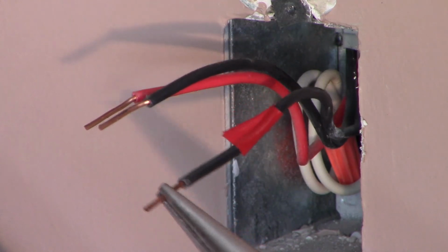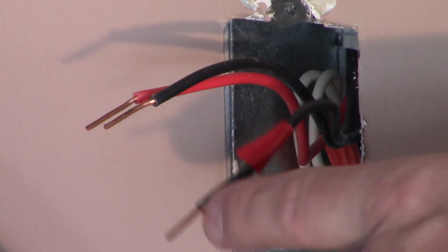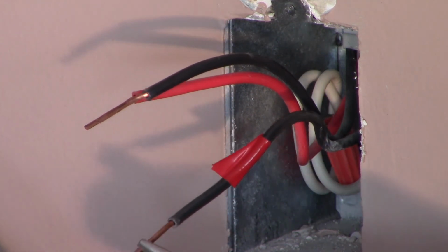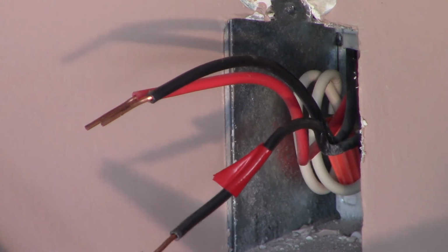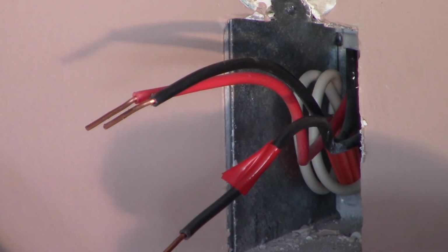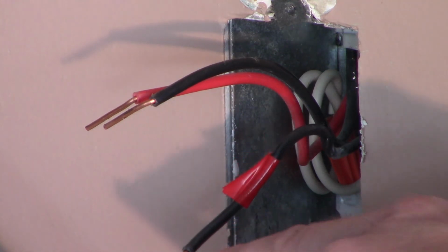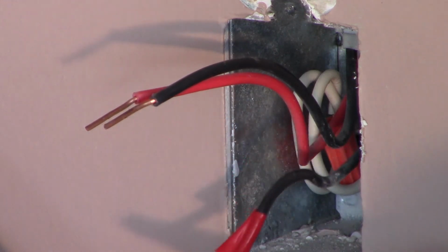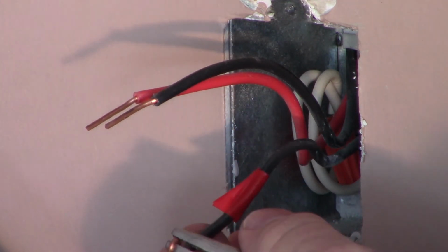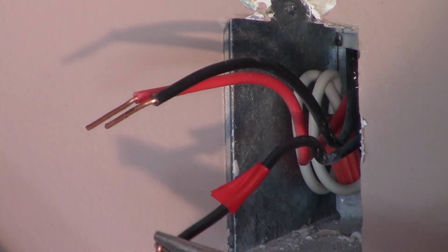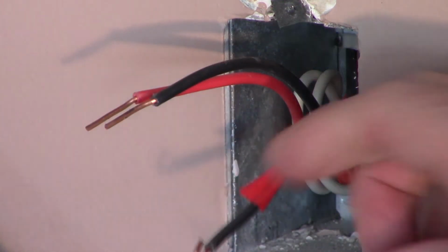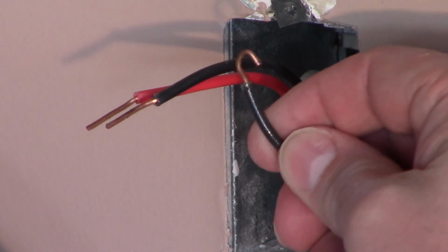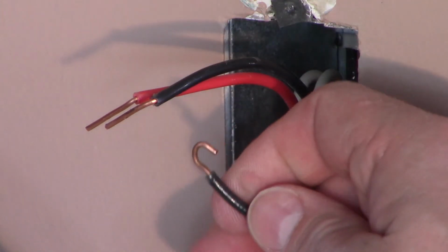So what I do with these, make sure you have at least half an inch of wire sticking out, which we do. Just simply take a needle nose pliers. This is a pretty good trick. If you see there, just leave about a 1/16 or 1/8 of an inch just beyond the tip of the needle nose pliers. Squeeze onto it and turn the pliers completely all the way around, and then back about a quarter turn, an eighth of a turn, and you'll see it forms a beautiful little loop in the wire like that, which fits perfectly around a screw for a device. You see that?